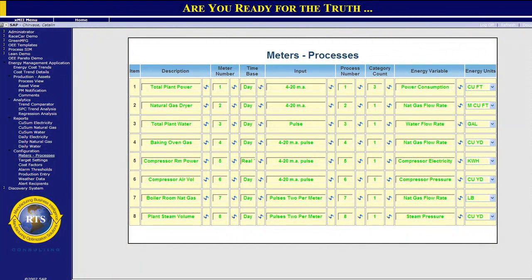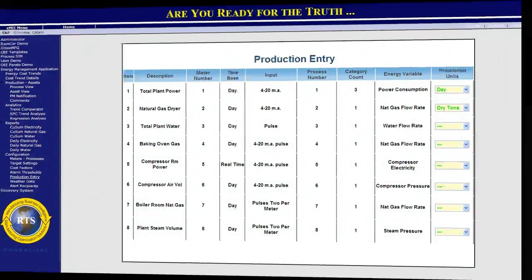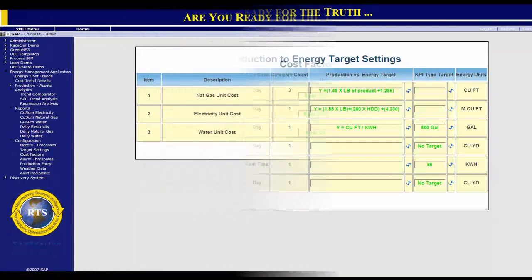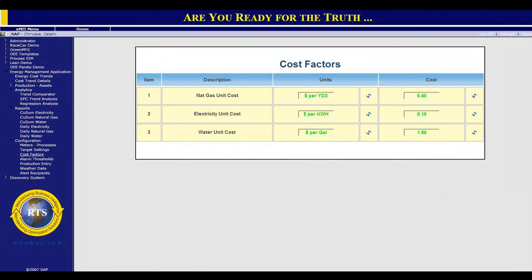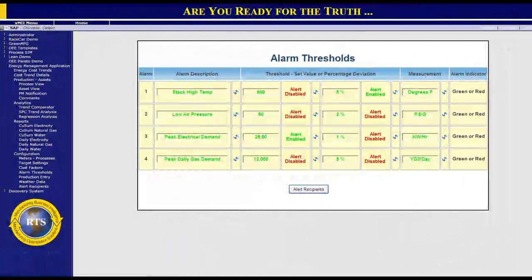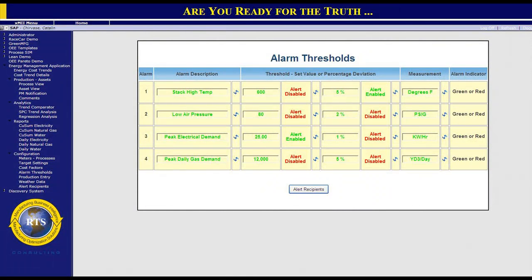A full complement of system configuration utilities is available within the composite application — configuration of meters, production volume configuration, and configuration of dynamic energy targets to production volume or product formulas. This enables the energy target to be dynamically self-adjusting based on production volumes or different SKUs being run. Energy costing screens can be updated via SAP ERP or manual updates. Alarm and email alerting can be set based on percentage value or a threshold, and email alerts can contain dynamic information from the anomaly so the recipient is aware of the specifics of the problem.